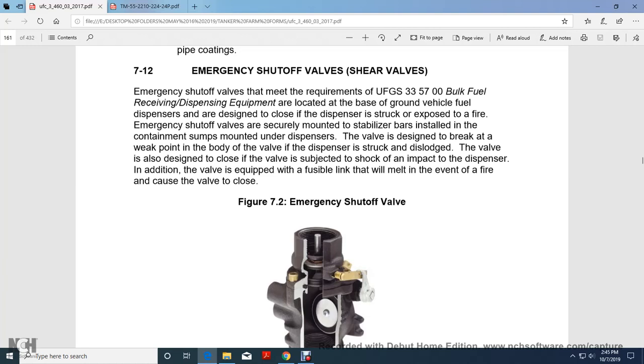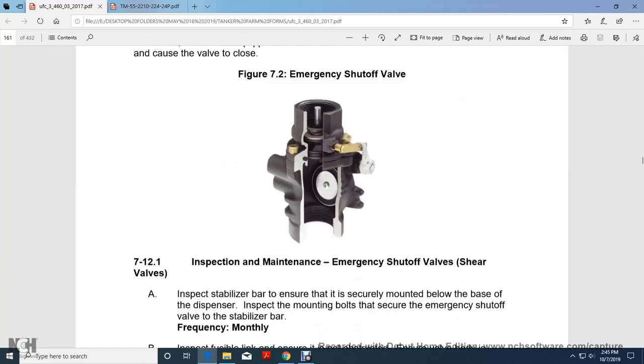The valve is designed to break at the weak point of the body of the valve if the dispenser is struck and dislodged. The valve is also designed to close when subject to the shock of the impact of the dispenser. In addition, the valve is equipped with a fusible link that will melt in the event of a fire, causing the valve to close.